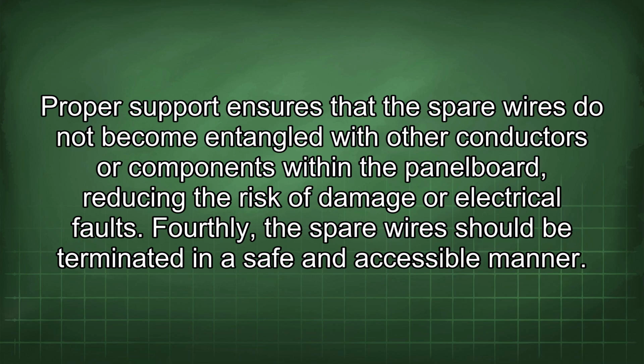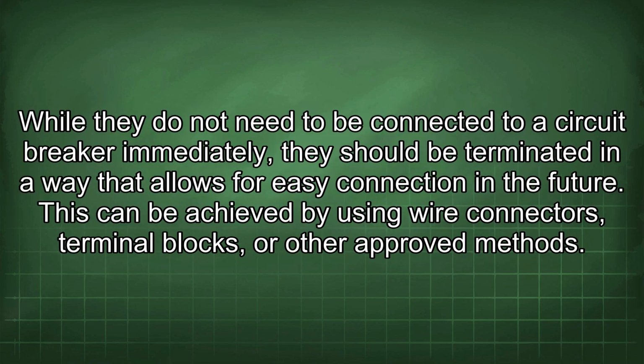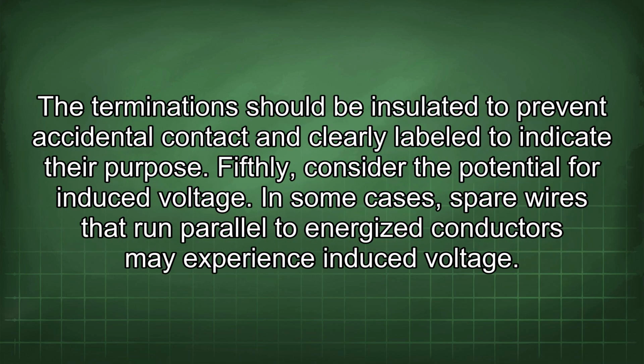Fourthly, the spare wires should be terminated in a safe and accessible manner. While they do not need to be connected to a circuit breaker immediately, they should be terminated in a way that allows for easy connection in the future. This can be achieved by using wire connectors, terminal blocks, or other approved methods. The terminations should be insulated to prevent accidental contact and clearly labeled to indicate their purpose.